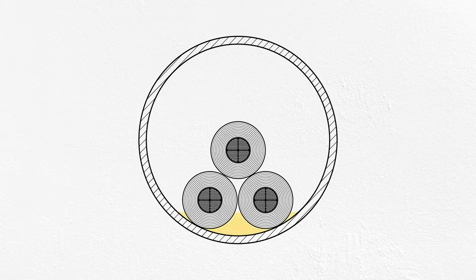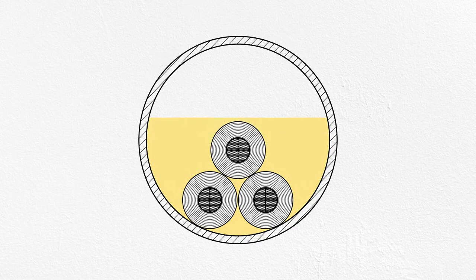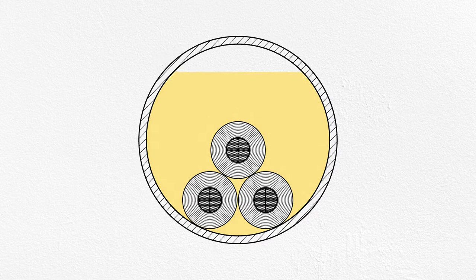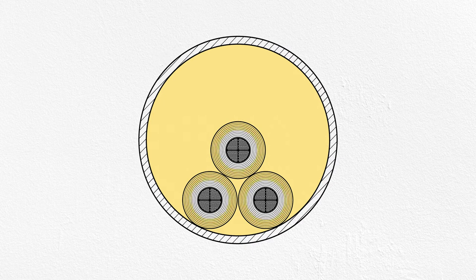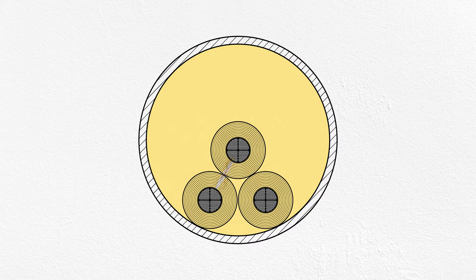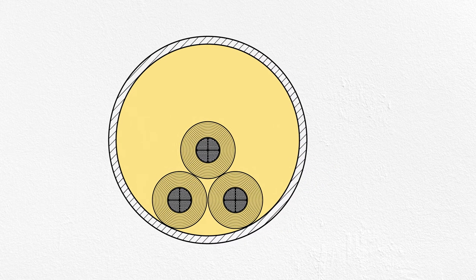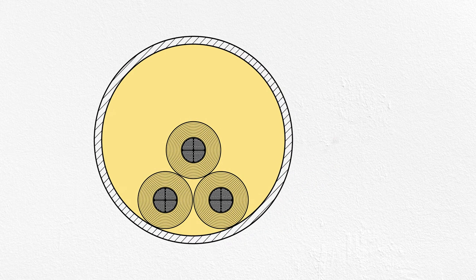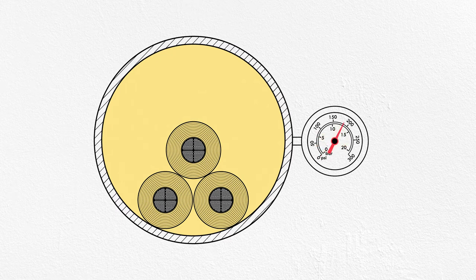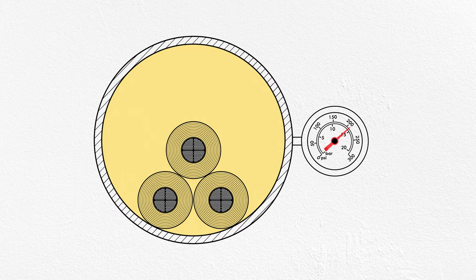At the same time, the oil works as a heatsink to carry away heat generated from losses in the conductors. It is critical that the oil completely saturates the paper insulation and fills every nook and cranny within the pipe. Just like a hole in the plastic insulation around an extension cord, even a tiny bubble in the oil can create a place for arcs to form because of the extreme voltages. So, the oil inside the pipe is pressurized—usually around 14 times normal atmospheric pressure or over 200 psi—to ensure that no bubbles can form.